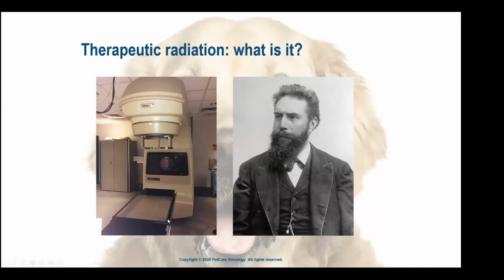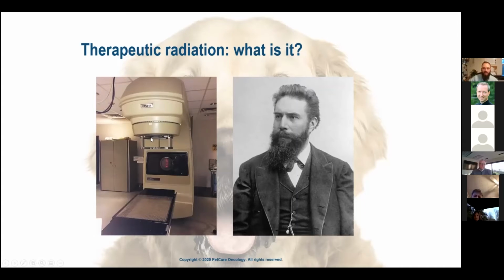Metal table, which is now replaced by carbon fiber, but you can see that there's no multi-leaf collimator on this machine. So basically you had your X and Y jaws, a very square or rectangular field. If you wanted to shape the radiation beam, you had to slide an acrylic tray in here with lead blocks and thumb screws to be able to shape the radiation beam.